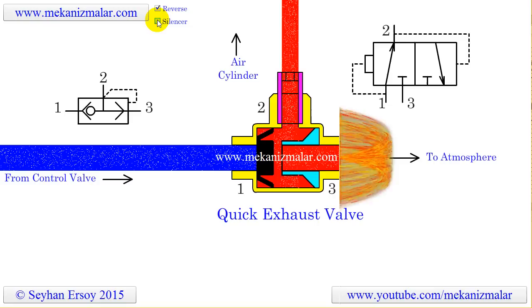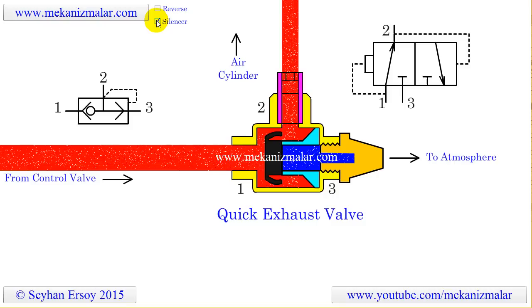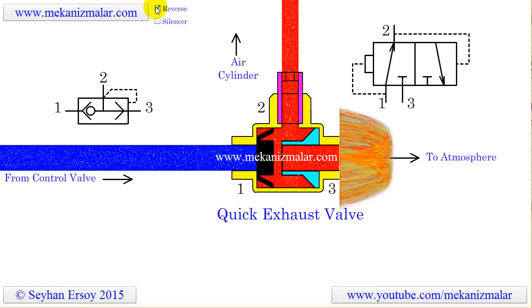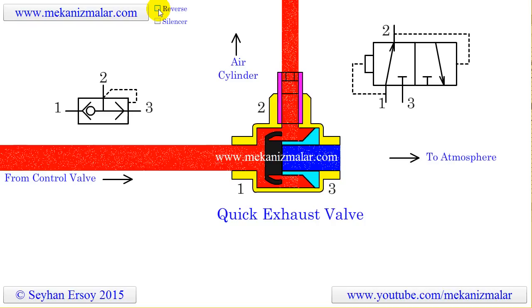If we want slow forward and very rapid return speed for the piston, one way to accomplish this is by using a very large control valve along with a speed control valve to regulate the forward speed. However, by using a quick exhaust valve, we can accomplish the same task with a small control valve.